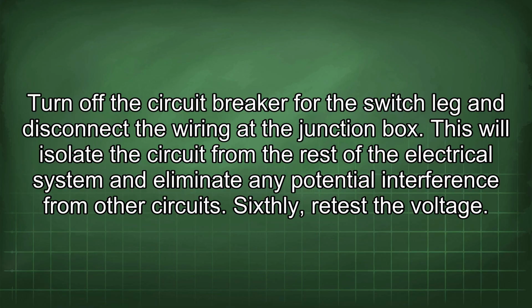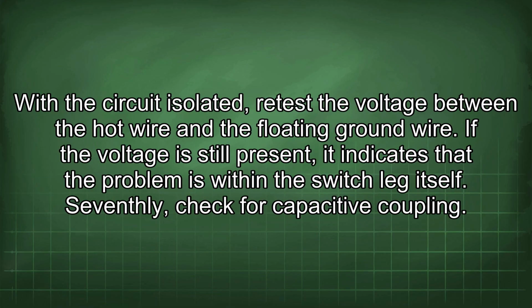Sixthly, retest the voltage. With the circuit isolated, retest the voltage between the hot wire and the floating ground wire. If the voltage is still present, it indicates that the problem is within the switch leg itself.